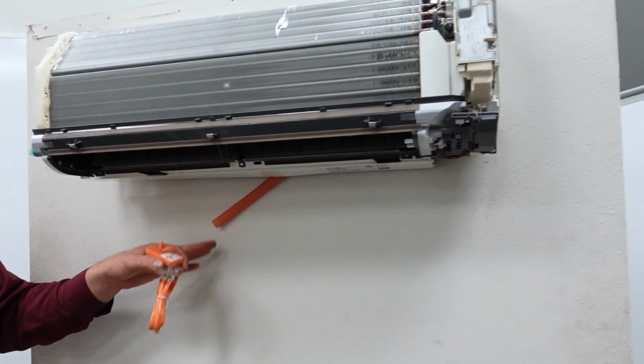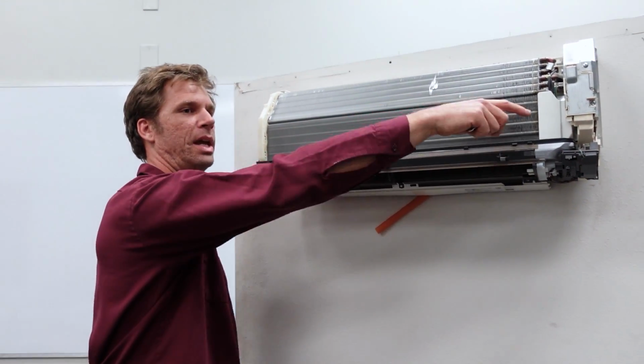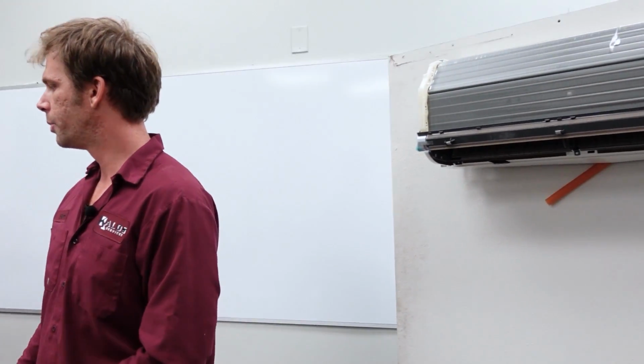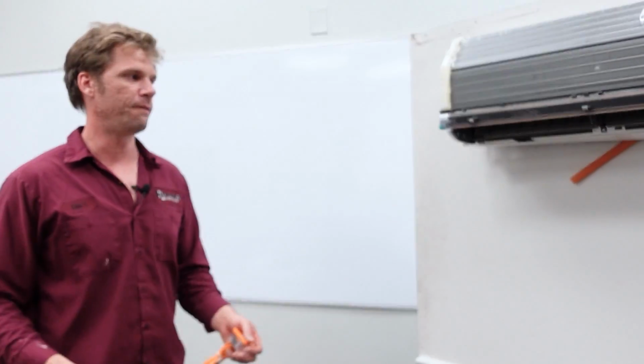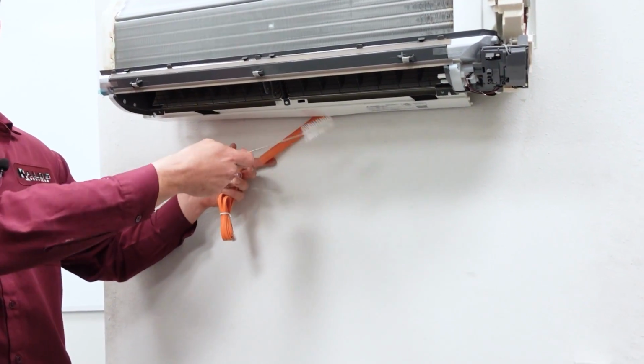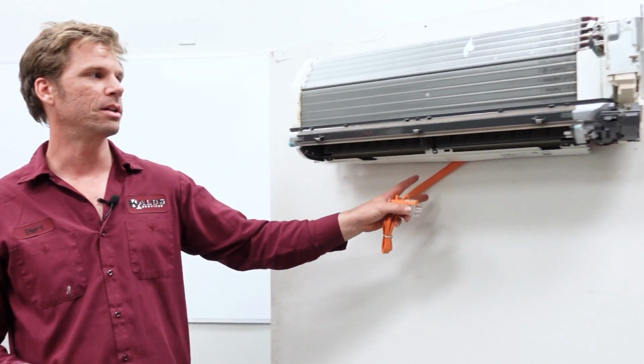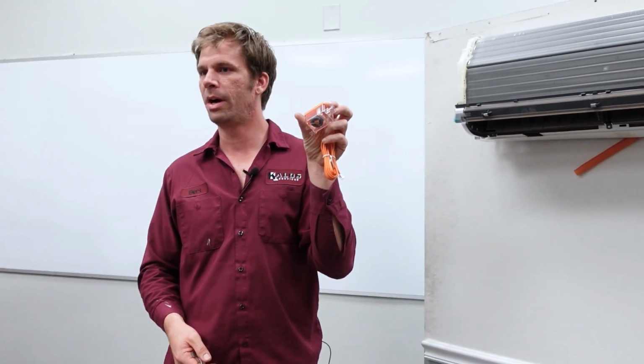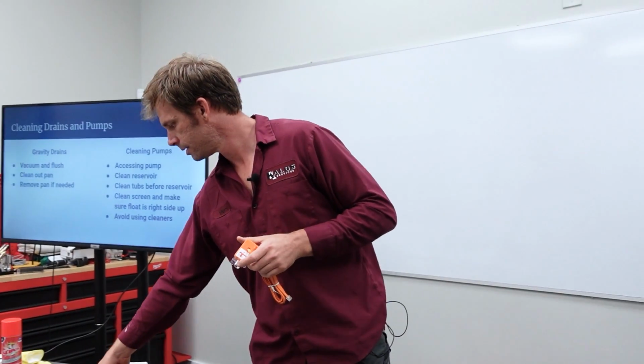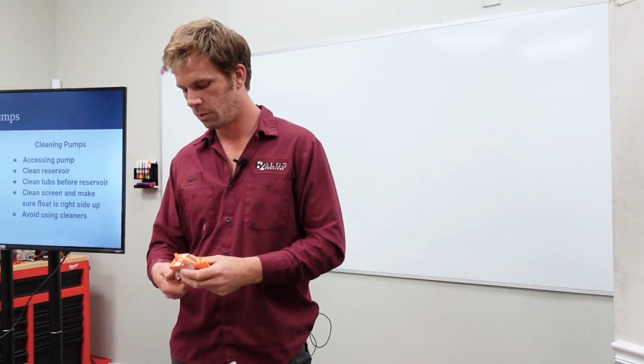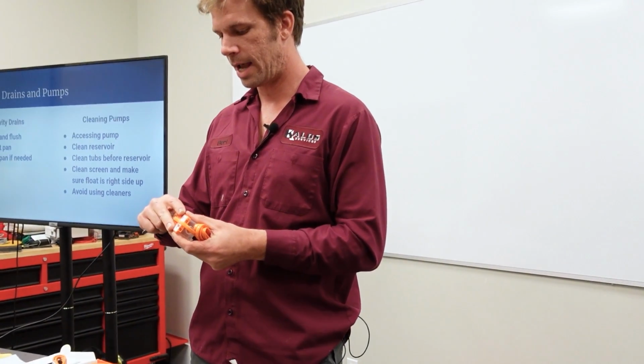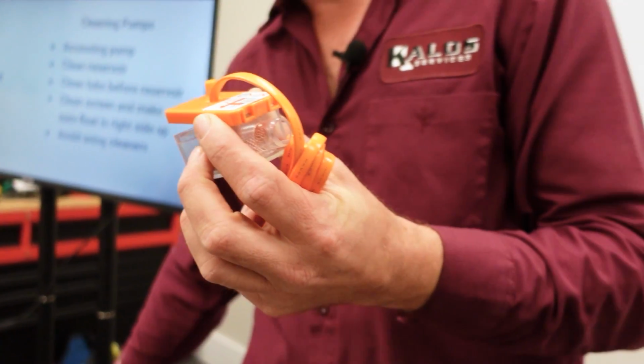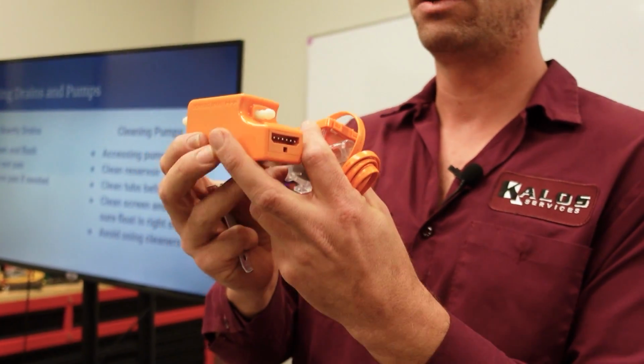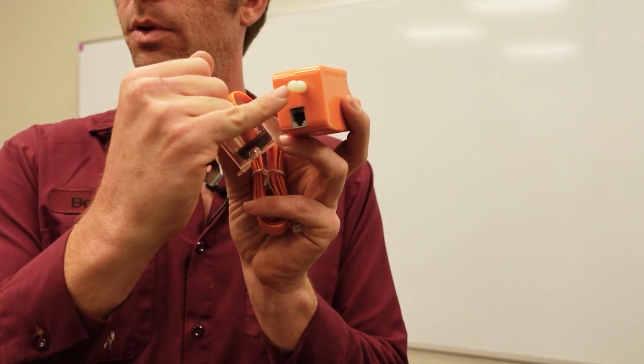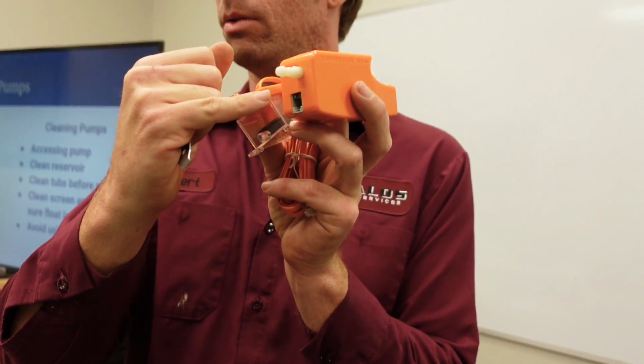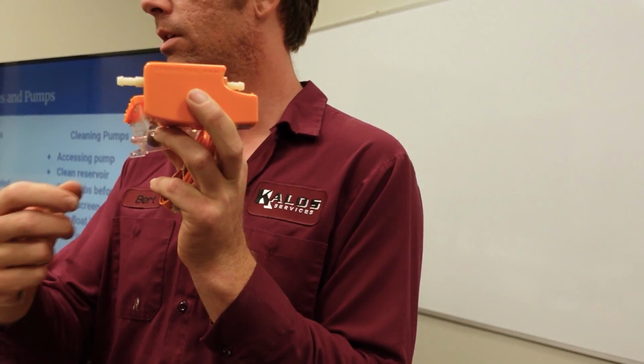Now, I will personally bring a vacuum inside, hook up, flush my pan, flush this all out. I'll take a brush, if it's gunky or nasty at all, and push it up in there and try to get that clean. So anything that I can clean is going to extend the life of my pump and help it operate better. So a pump often will fail because it's actually got so much junk built up that it's pulling in to the pump motor. And if you've ever taken one of these apart, it's a pretty small hole right there that everything's got to go through. So it doesn't take a lot of algae or a hard chunk of something to clog it up.